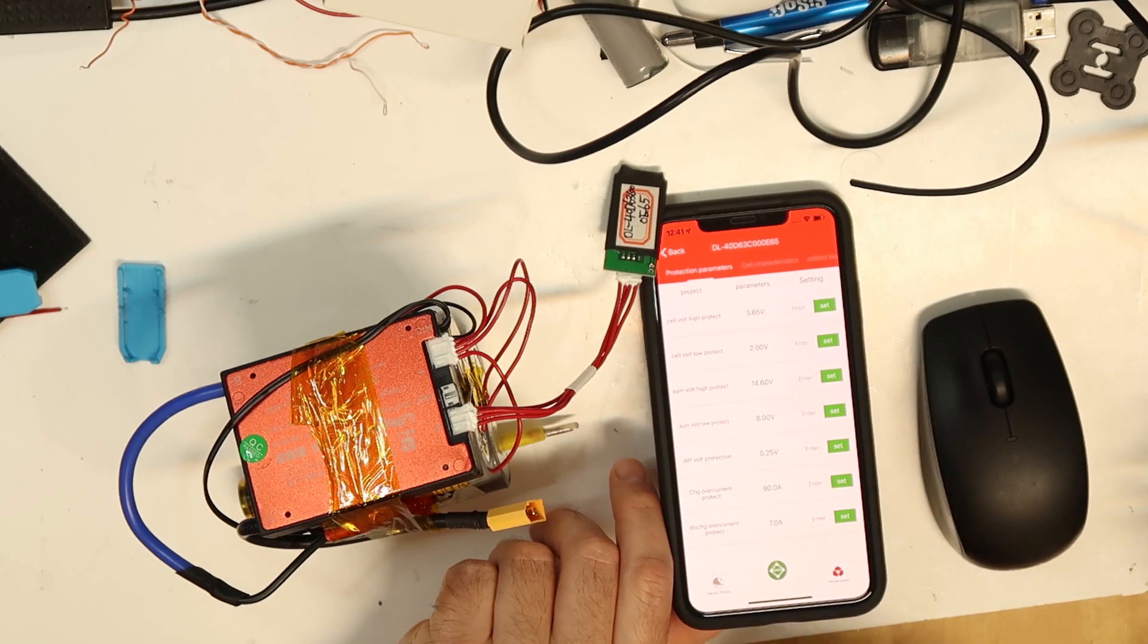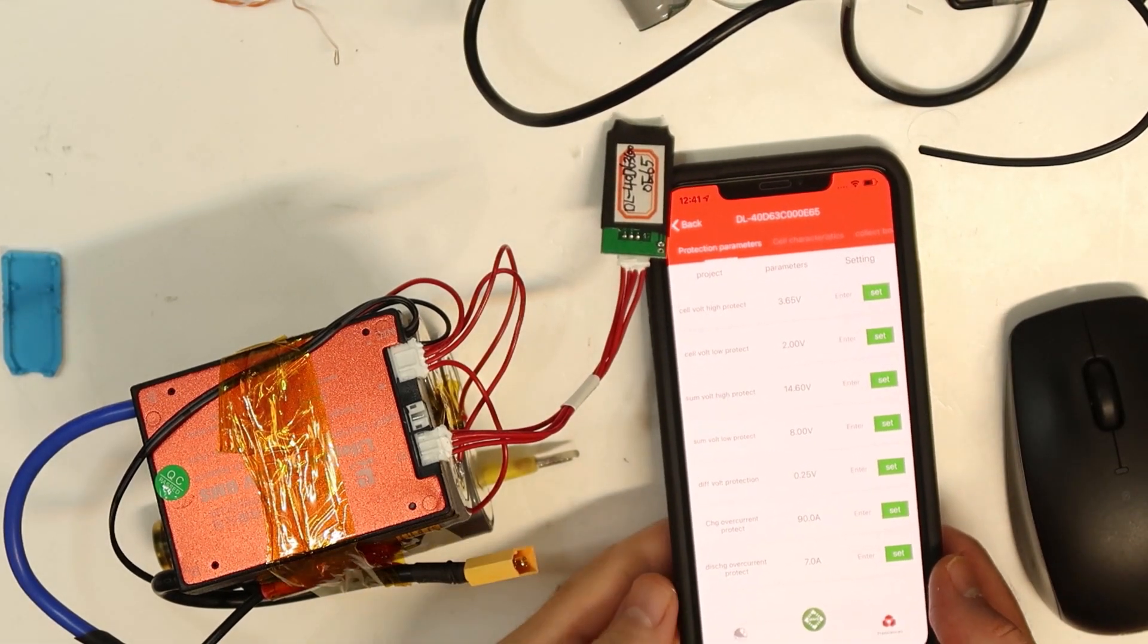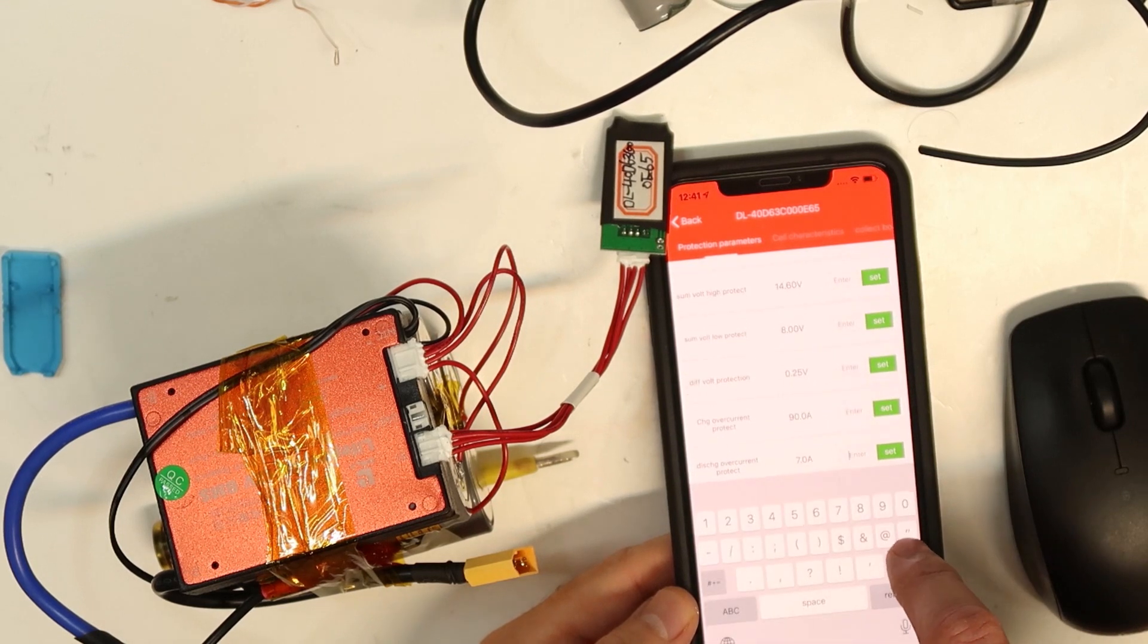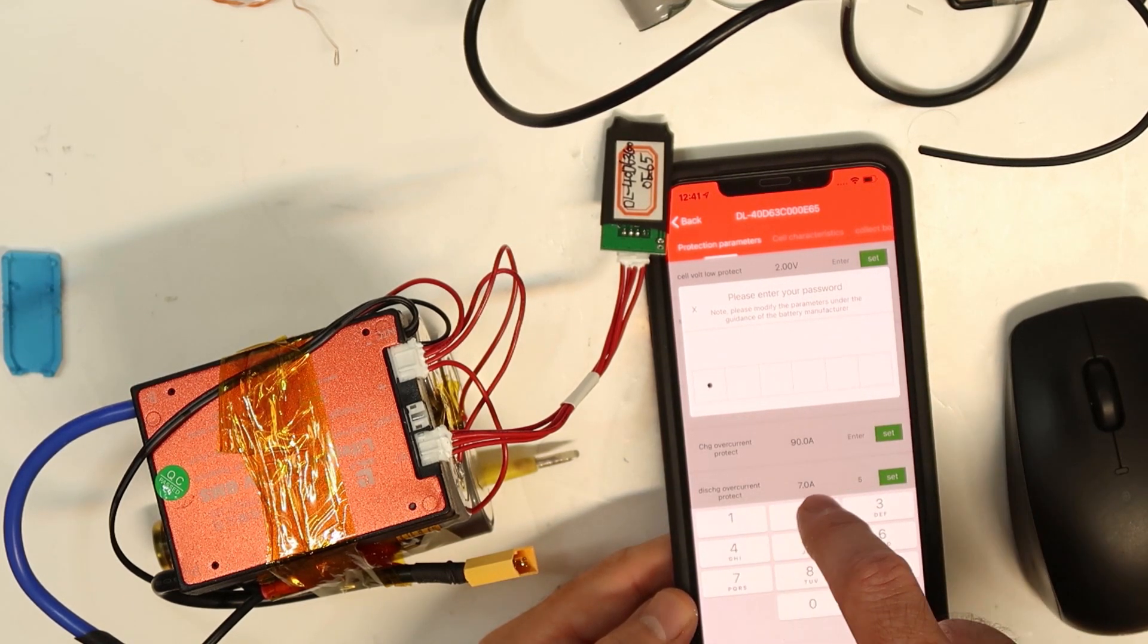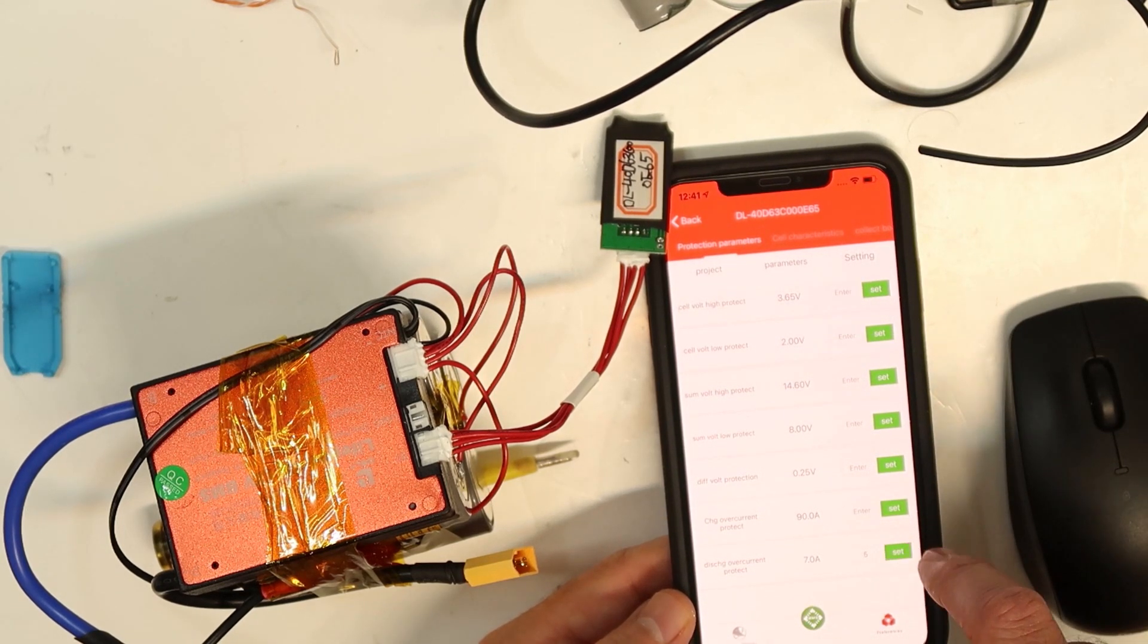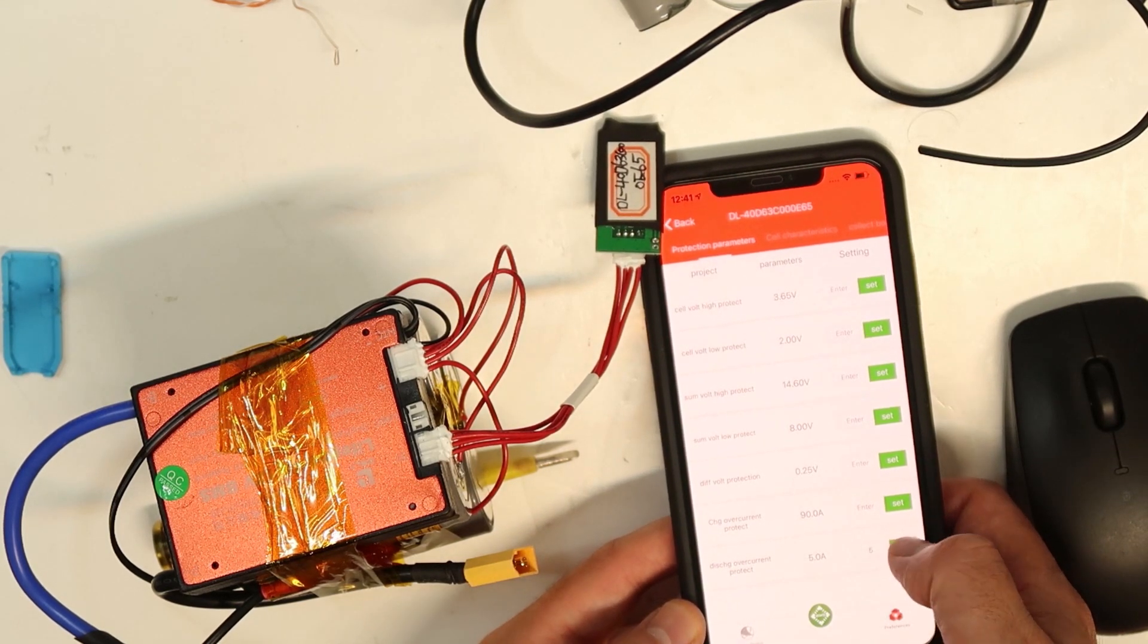If I go to the settings, this is maybe one of the advantages of this one. You can set the discharge current - now it is seven amps. You can enter a number, let's say I will put five, and then set. Then it asks for the password - the password is one to six. You set it.